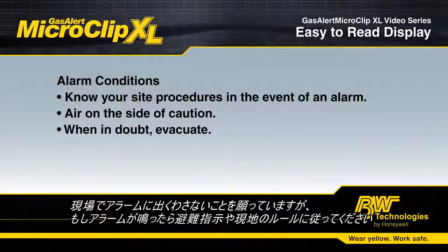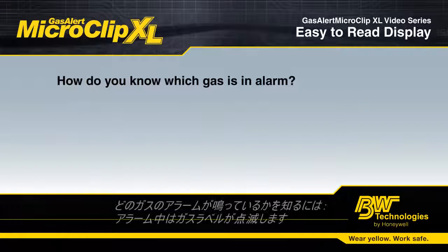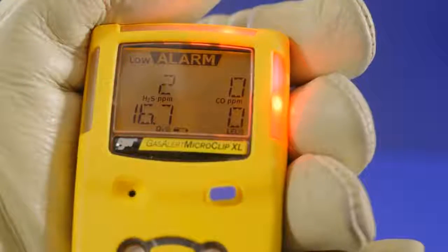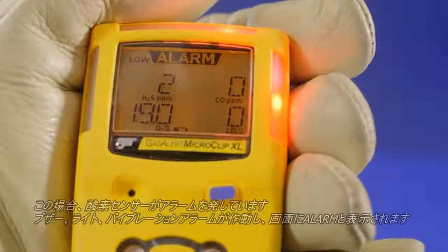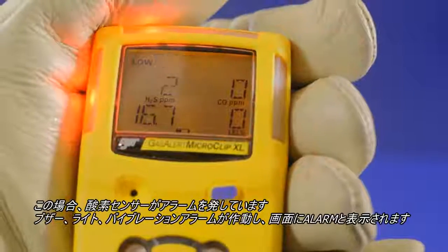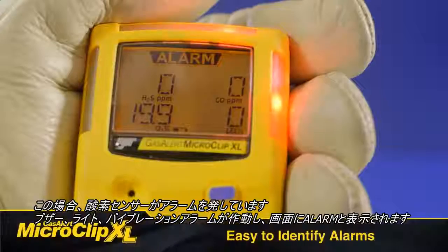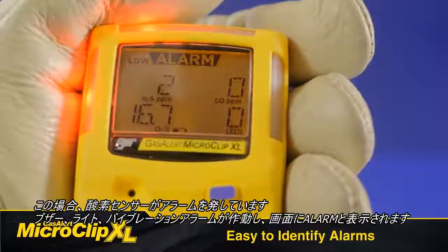Hopefully, you never encounter an alarm. In the event you do, follow your evacuation protocols and your site procedures. How do you know which gas is in an alarm condition? The gas below the reading will flash. In this case, the oxygen sensor is in alarm. In addition to the audible, visual, and vibrating alarm, alarm will flash at the top of the screen.